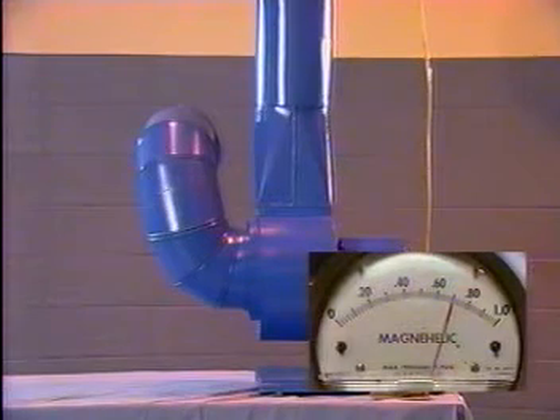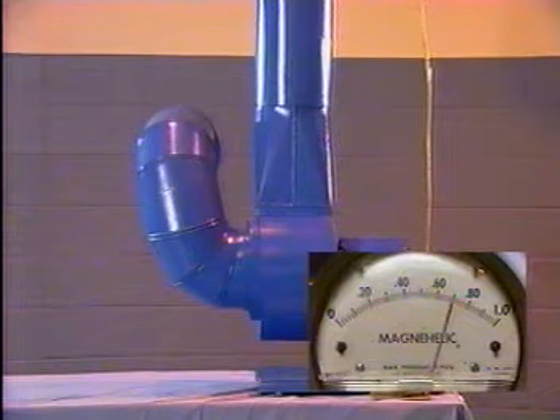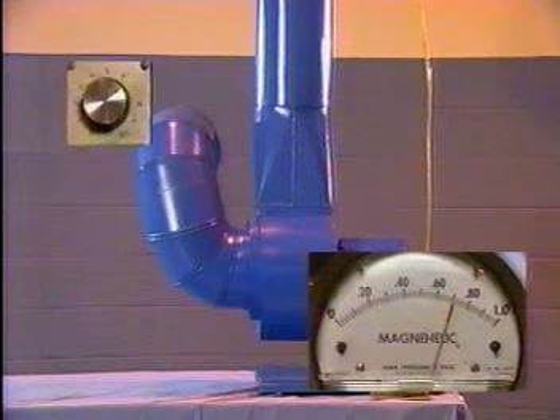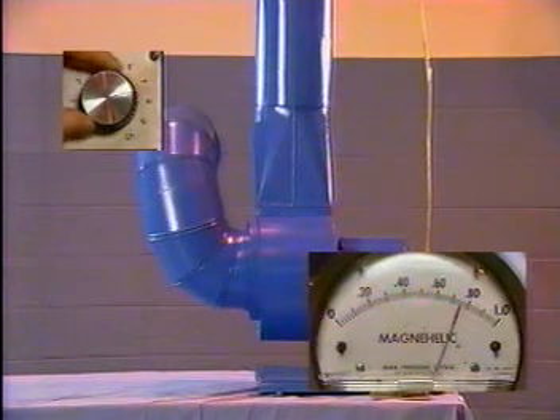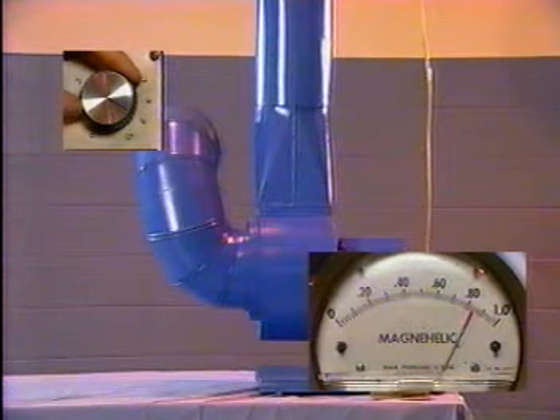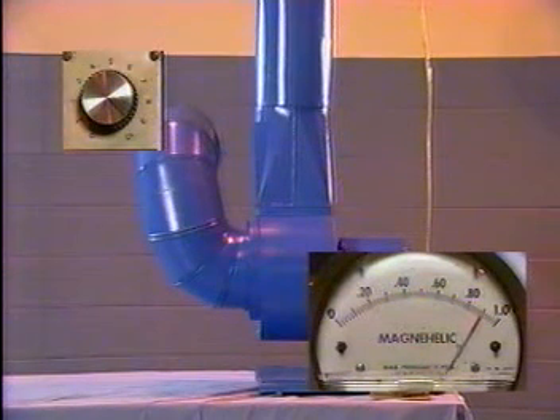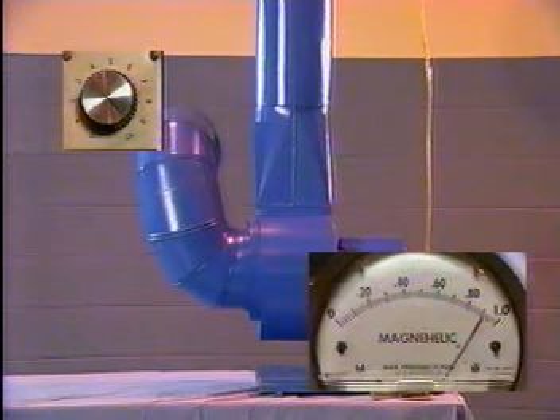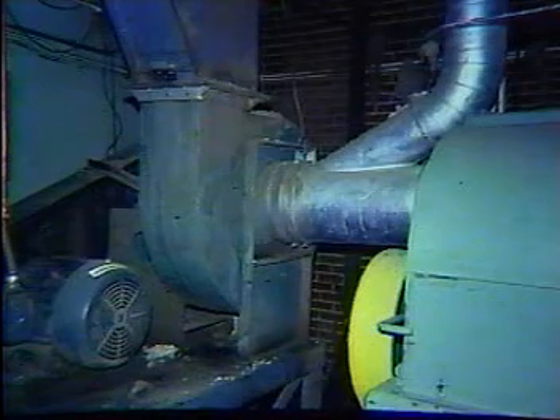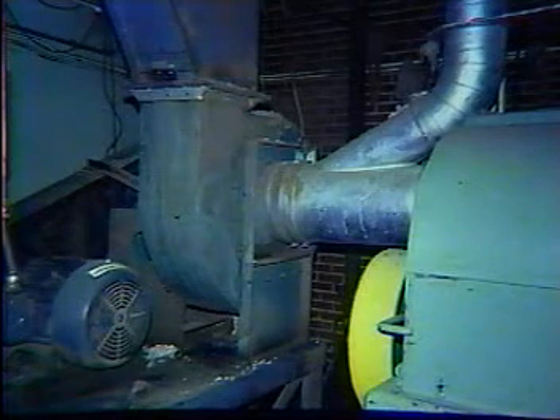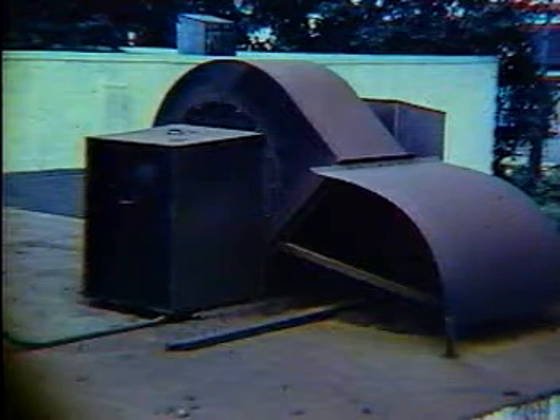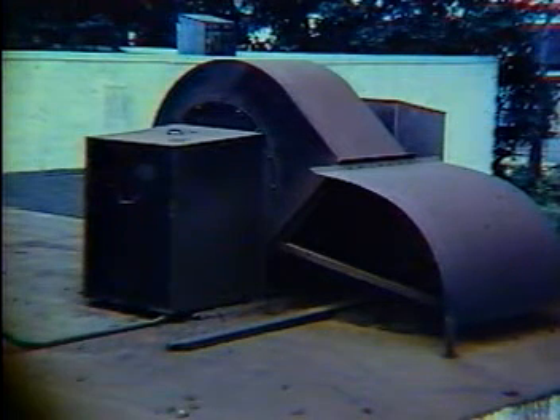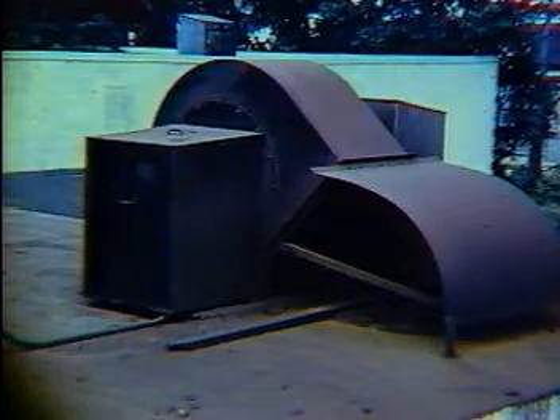Of course, even many of the worst designs can be made to work by increasing RPM. By increasing fan speed, it's possible to meet airflow requirements. Problem is, you pay the penalty for such system effects in the form of higher electrical bills. When a system is not performing up to anticipated standards, the tendency is to blame the fan. That's natural. It's difficult to see how non-moving ductwork could be part of the problem, but it is.